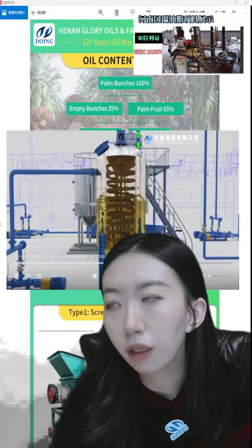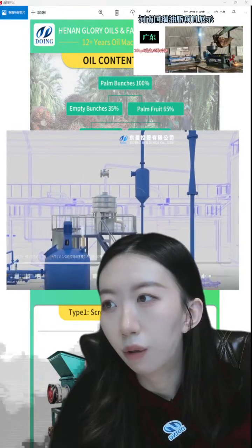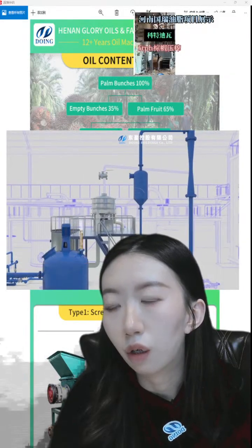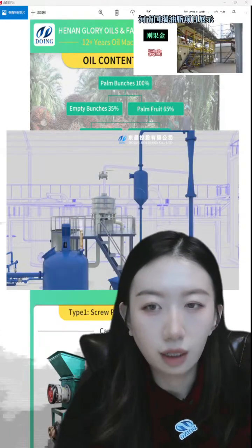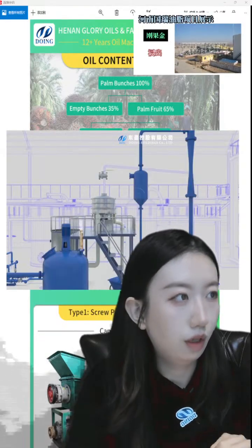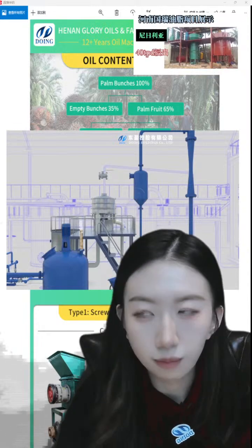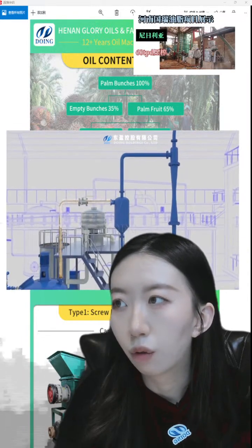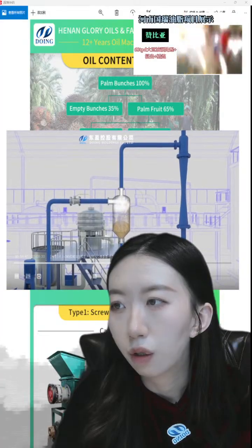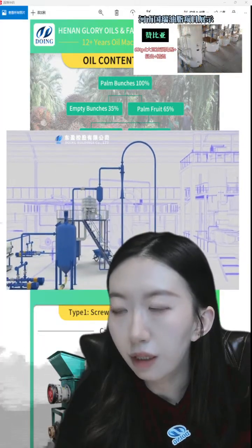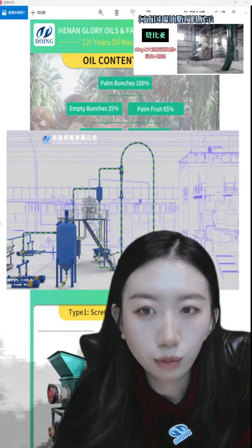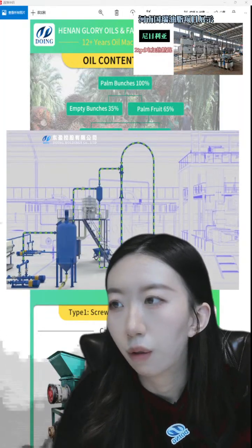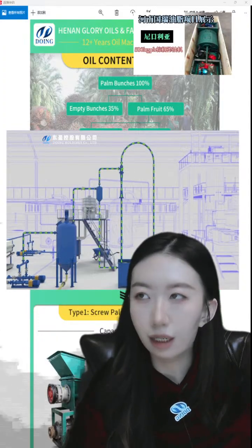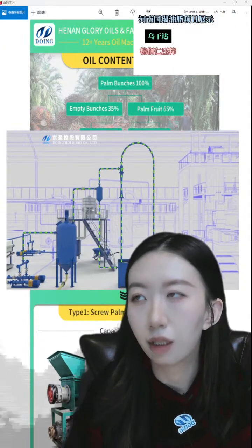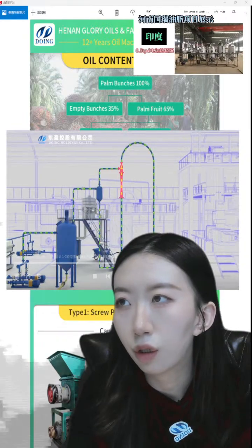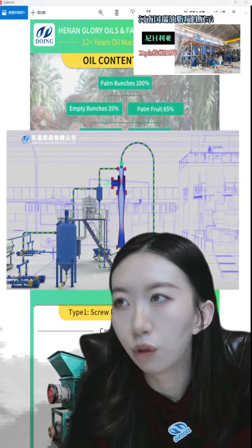During boiling, the water vapor will go up to the oil-water separator, and the oil vapor will go up to the separator together. In this separator, the oil will be forced down to collect, while the water vapor still goes up to the water jet pump.